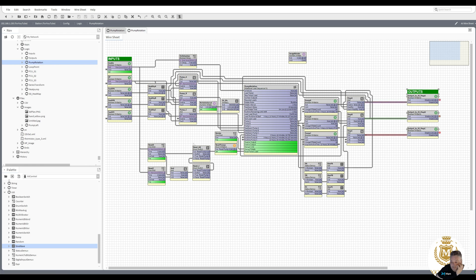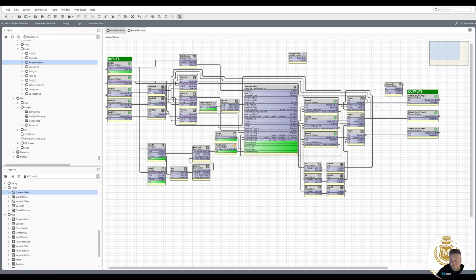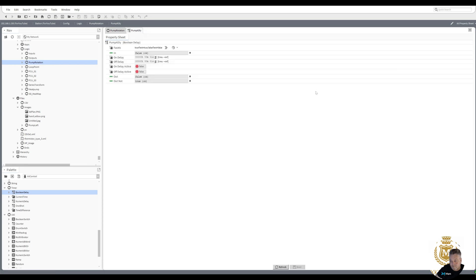What I mean by that is if we take in a timer and a boolean delay — it's already just changed over now, so you can see pump B is now changed over to running. I'm going to do an off delay — in fact we'll do an off delay of one minute, so when we're changing over there'll be two pumps running for at least one minute.